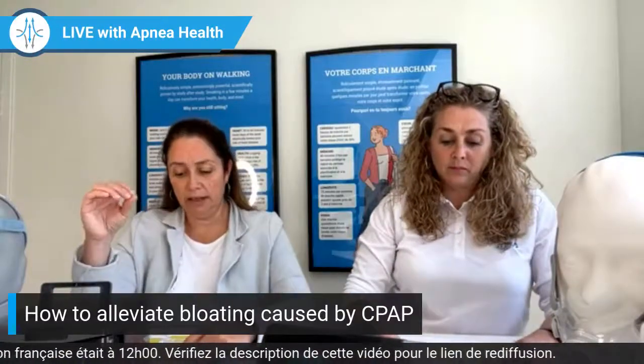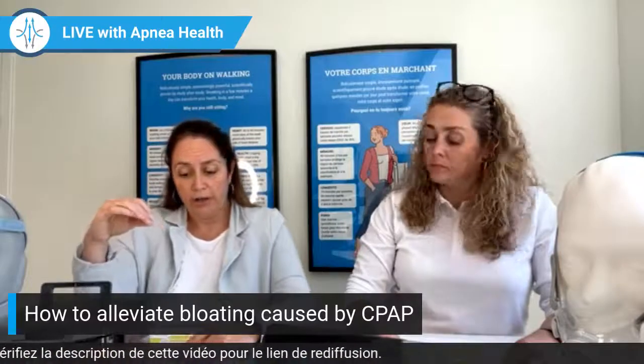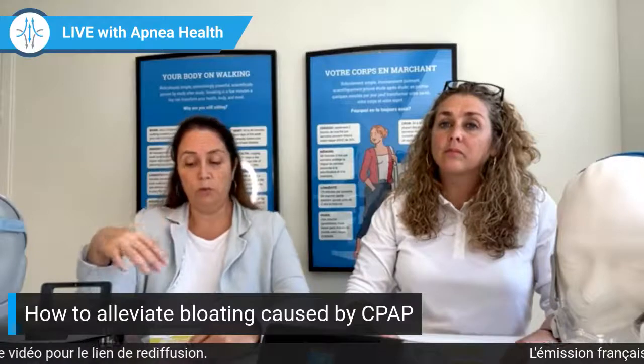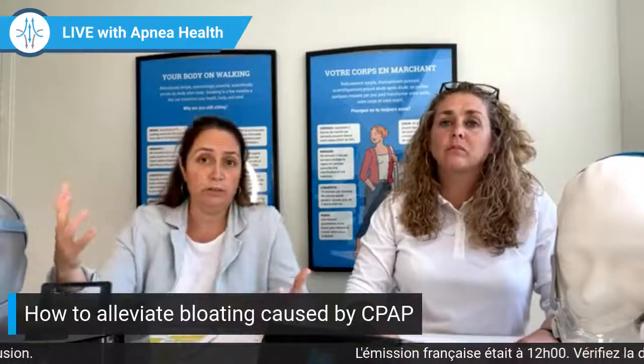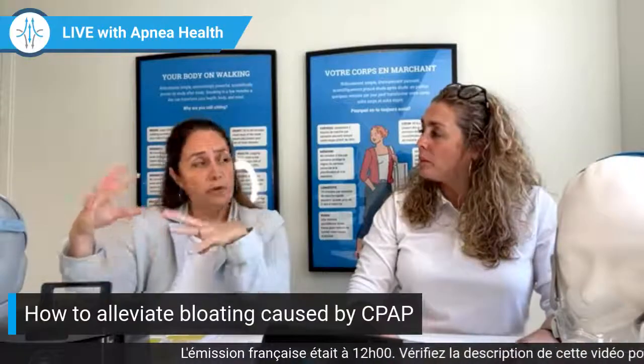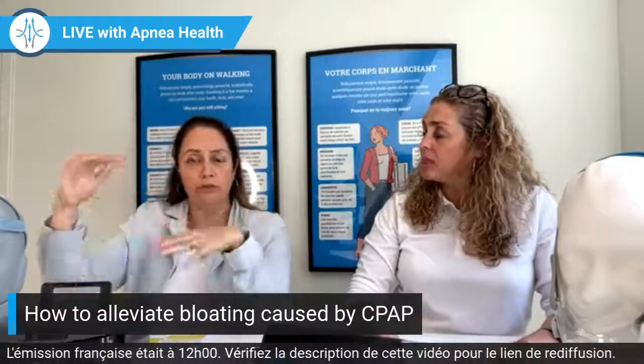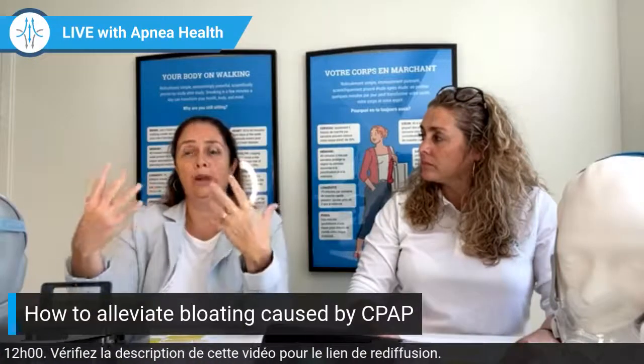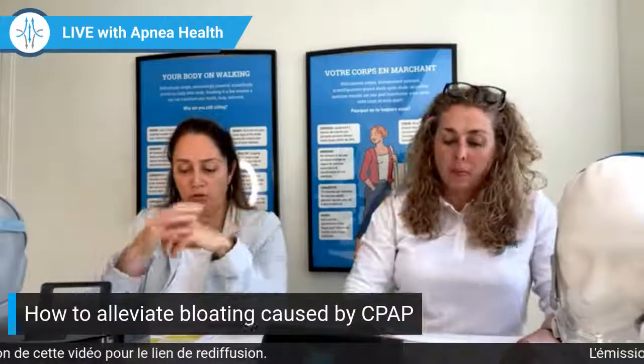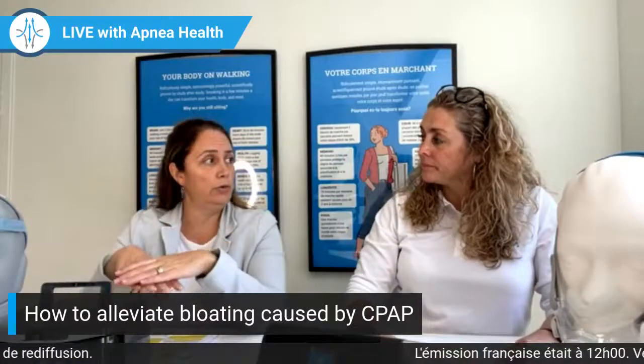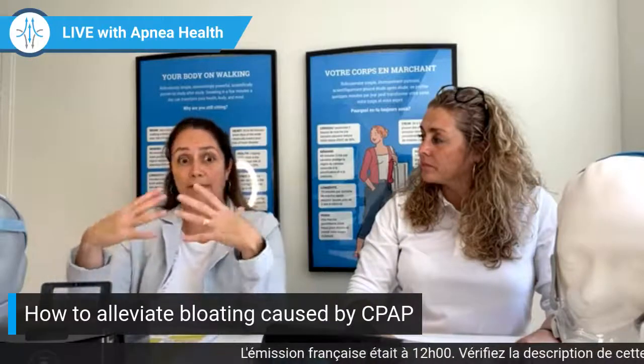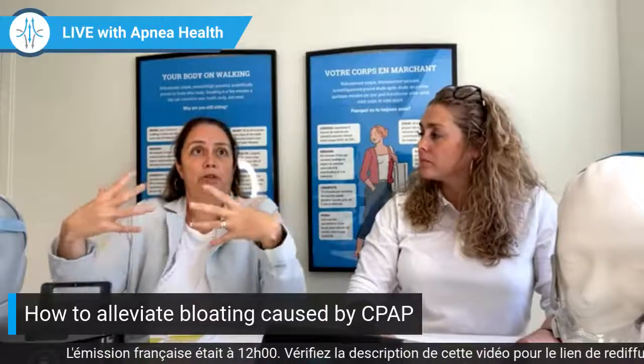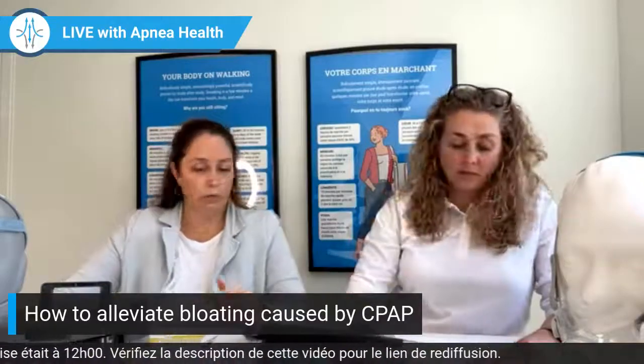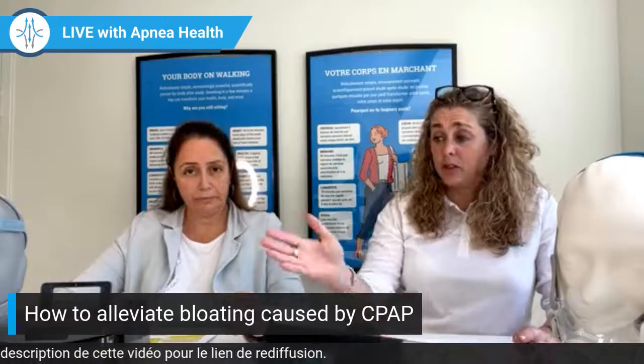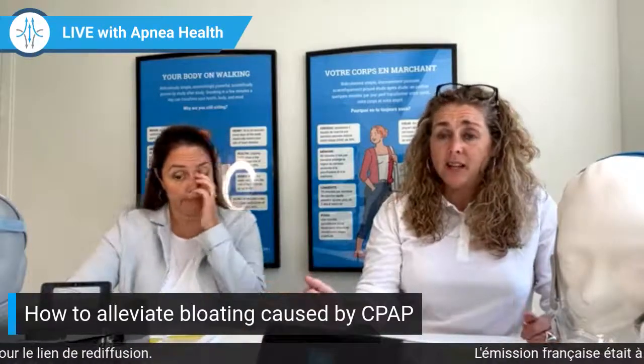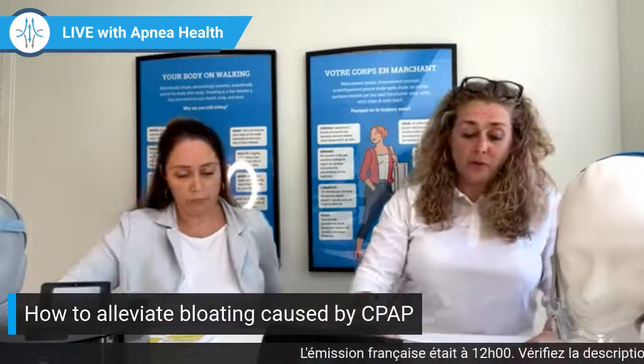The device will quickly decrease the pressure to the lowest and most comfortable level when you wake up during the night. Because of course, if you use a CPAP with a variable machine, the machine will go up and down during the night, and it can be strong, especially when you're waking up. So with SenseAwake, the machine will lower the pressure, and then you won't wake up to that strong pressure, open your mouth, and swallow air, which gives you that problem with aerophagia. Okay, so that's good to know for people with that device. SenseAwake can be really helpful for them. Yes.